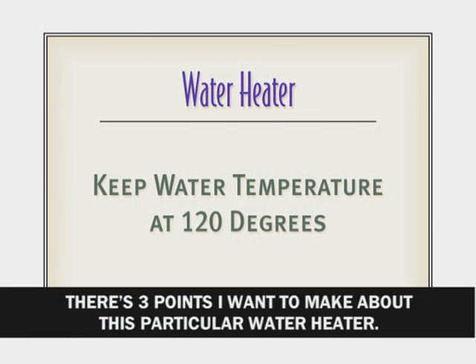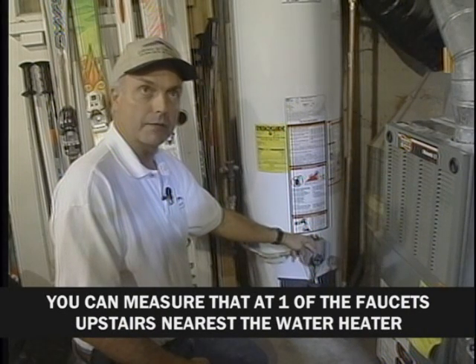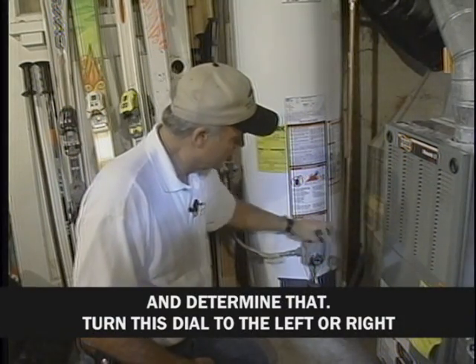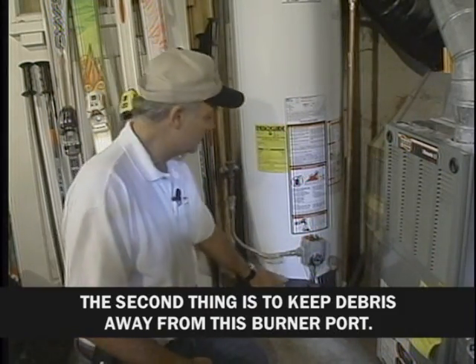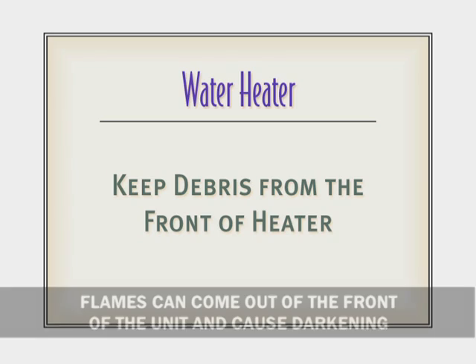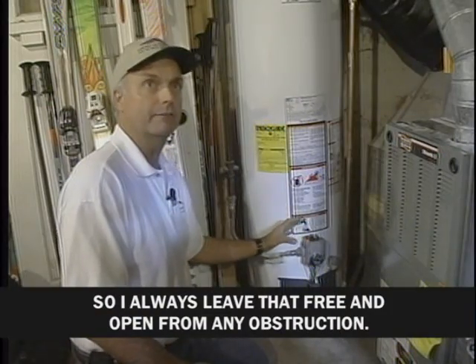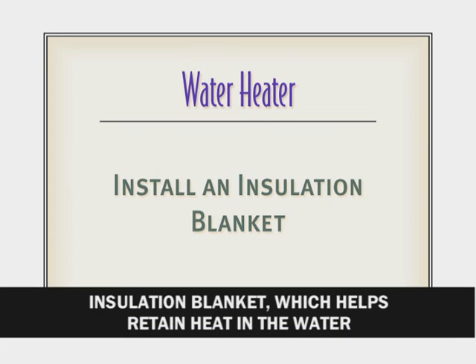There are three points about this water heater. First, turn down the thermostat to get a 120-degree rating — measure that at a faucet nearest the water heater and turn the dial to the left or right accordingly. Second, keep debris away from the burner port as a safety issue; delayed combustion can cause flames to come out the front and catch things on fire. Third, consider adding an insulation blanket, which helps retain heat in the water where you want to keep it.